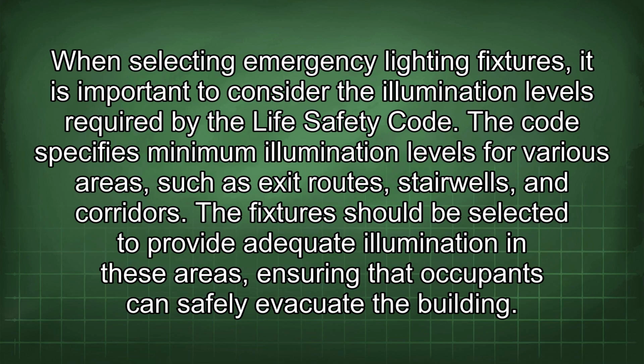When selecting emergency lighting fixtures, it is important to consider the illumination levels required by the Life Safety Code. The code specifies minimum illumination levels for various areas, such as exit routes, stairwells, and corridors. The fixtures should be selected to provide adequate illumination in these areas, ensuring that occupants can safely evacuate the building.